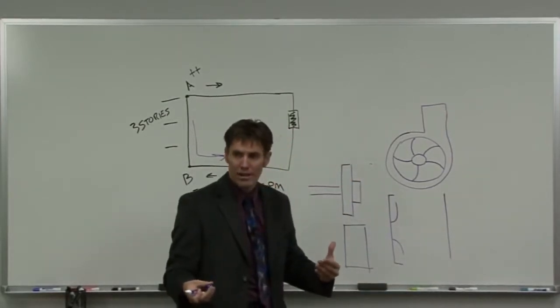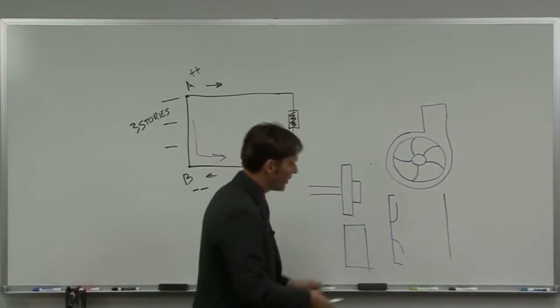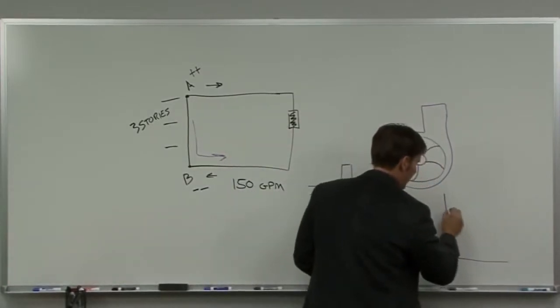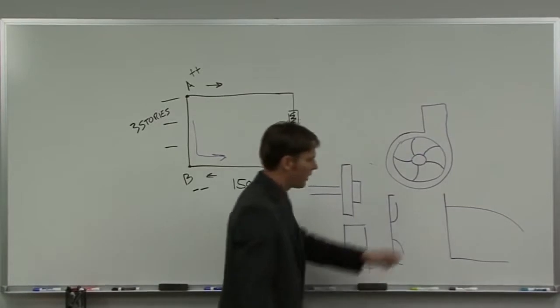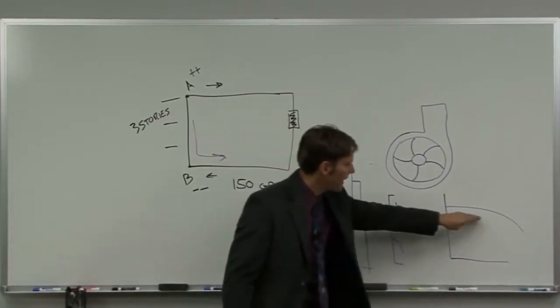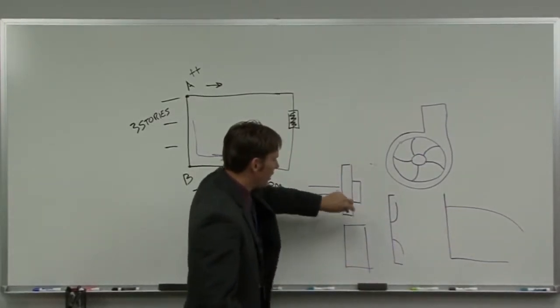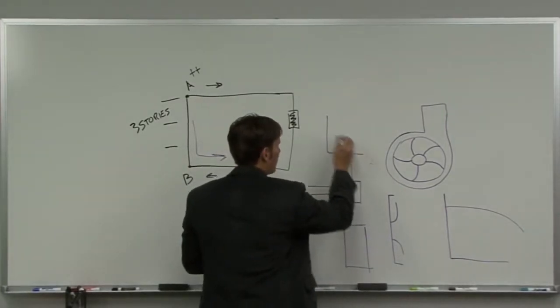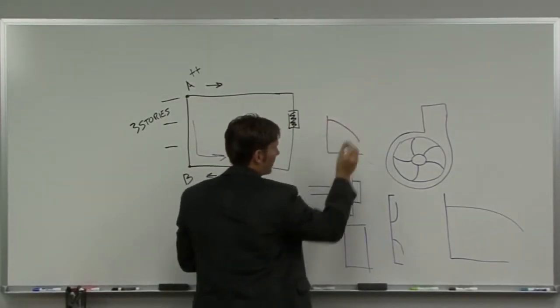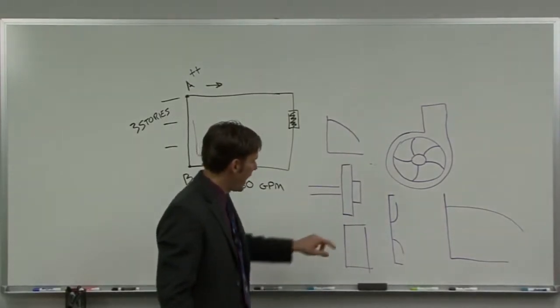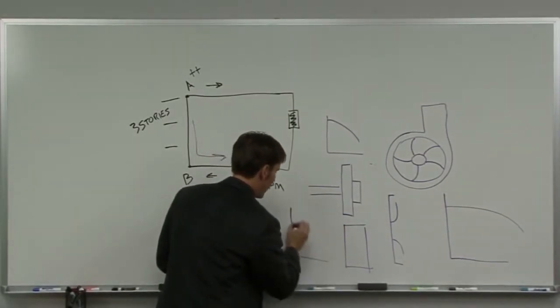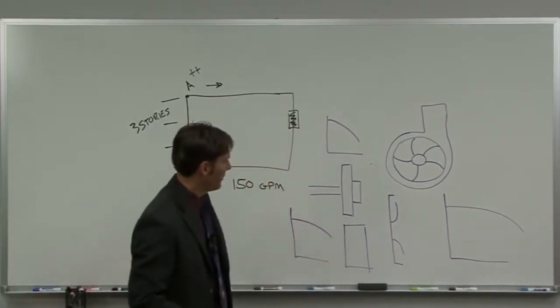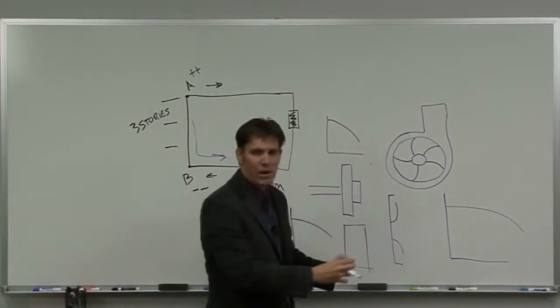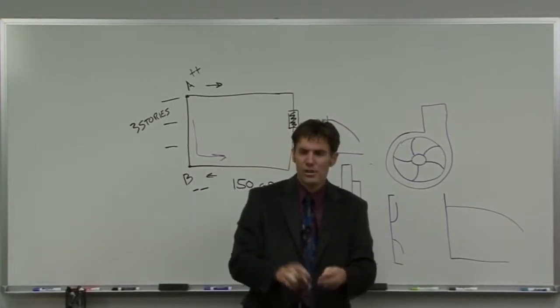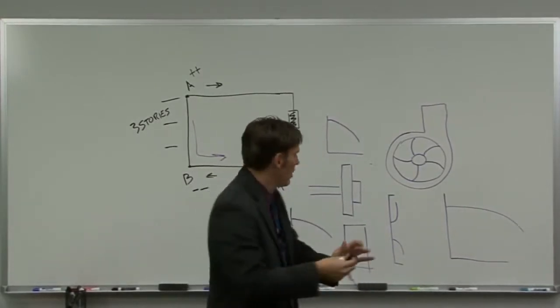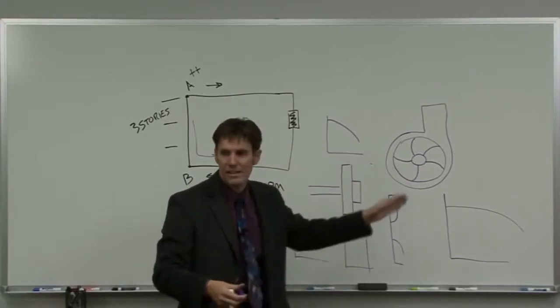Typically in a closed loop hydronic system, we'll be using closed face impellers. But an open face impeller will typically give you a much flatter curve. Now, we're going to talk about curves in just a minute, but it'll give you a flatter curve. A thin closed face impeller will give you a likelihood of more of a steeper curve. A fat impeller will also give you a more flat curve. So again, the design of this, whatever the manufacturer, whatever flow rates and pressures they're trying to get to, will define how they're going to design these components.